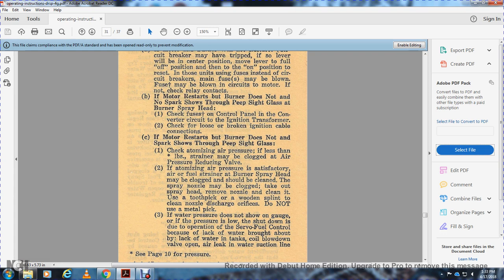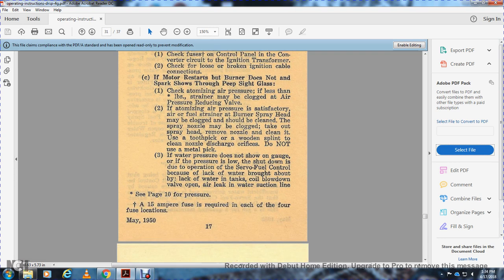Check the atomizing air pressure and the air supply. The fuel strainer or the burner spray head may be clogged and should be cleaned. Take out the spray head, remove the nozzle, and clean it with a toothpick or a wooden splint, or use a clean nozzle discharge. Do not use a metal pick. If the water pressure does not show on the gauge, or if the pressure is low, the shutdown is due to the servo fuel control operating because of a lack of water, brought about by a lack of water in the tank, the blow down valve opening, or an air leak in the water suction line.